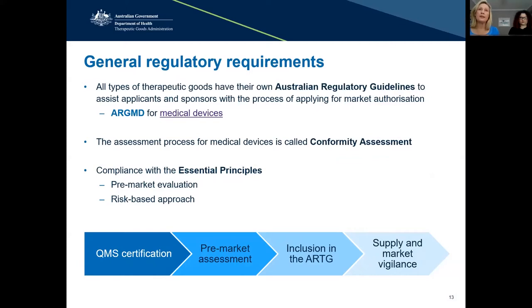We have an assessment process that manufacturers need to go through for medical devices called conformity assessment. This is how the manufacturer demonstrates compliance with the essential principles. There's pre-market evaluation, and TGA applies a risk-based approach. For really high-risk devices, it's a series of detailed steps the manufacturer has to go through. But for low-risk devices like PPE, the conformity assessment requirements are very low, mainly revolving around the manufacturer undertaking a self-assessment process to make sure they meet the requirements before applying to supply them in Australia.